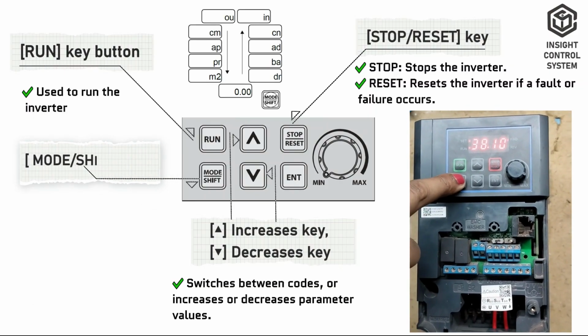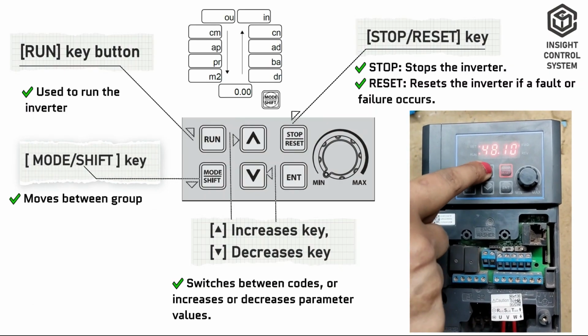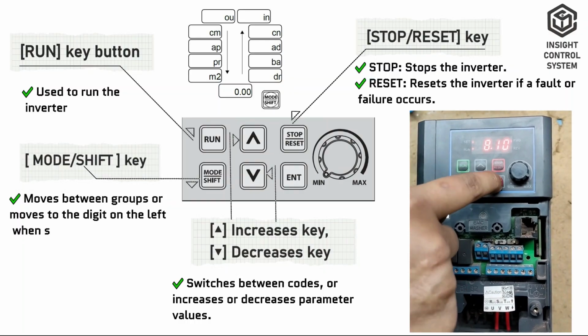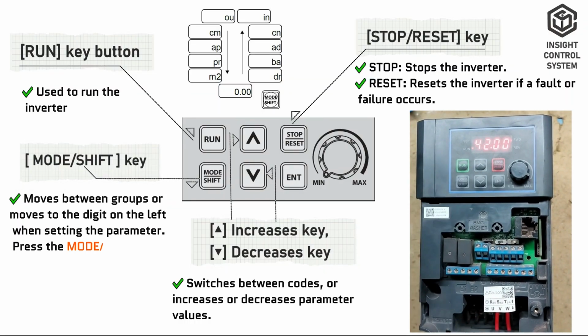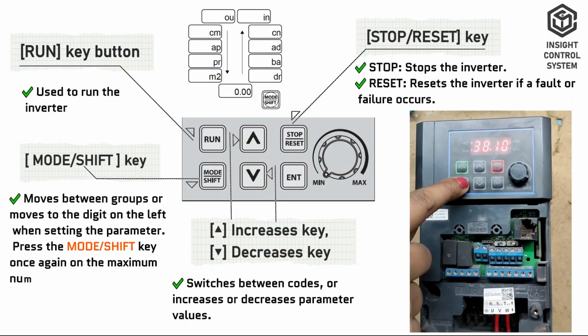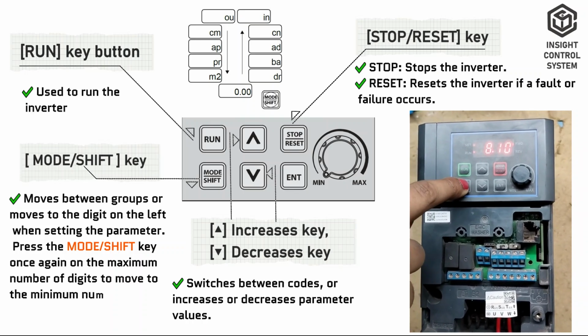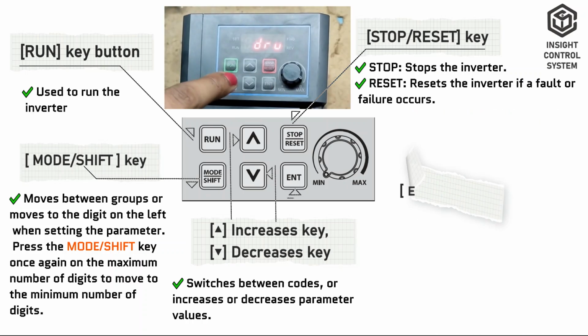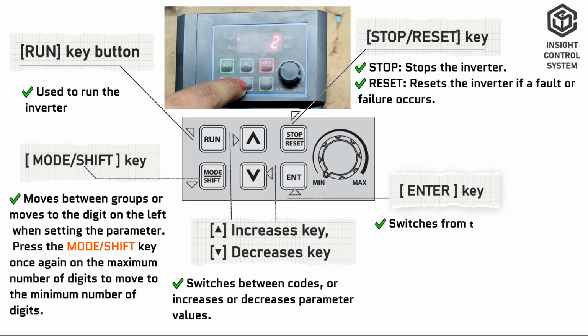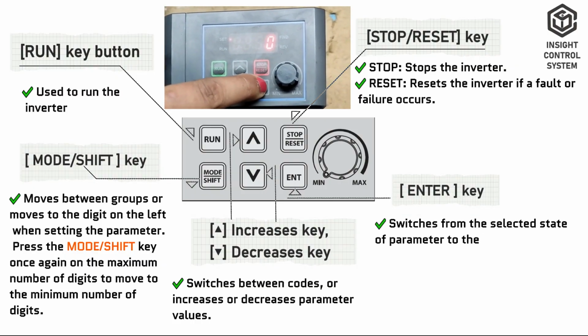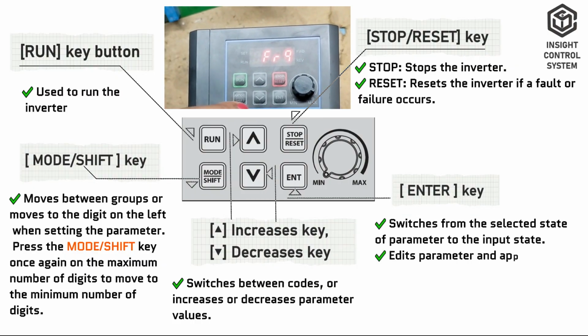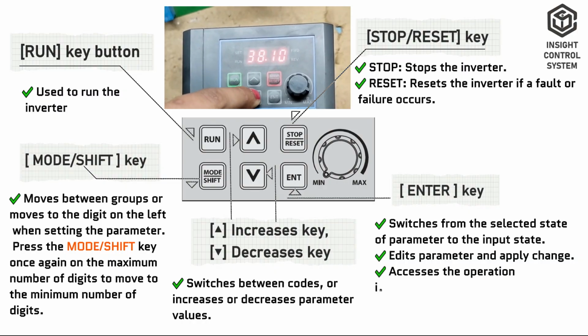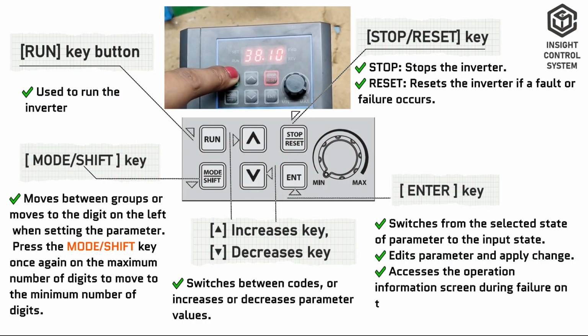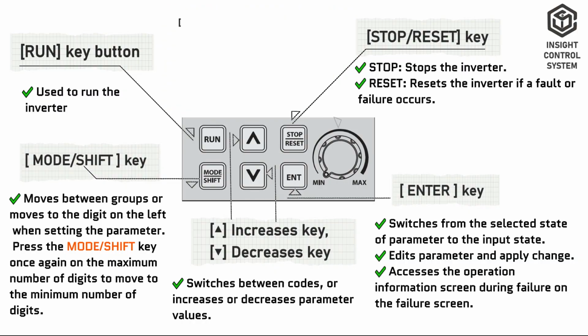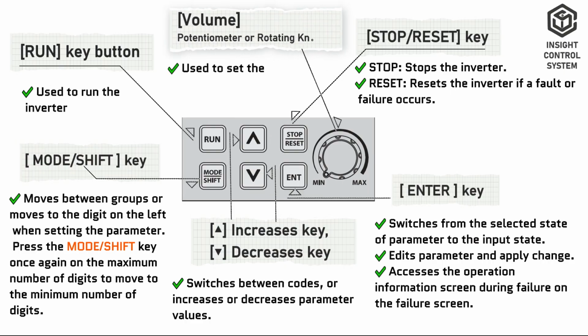This is mode or shift key button, moves between groups or moves to the digit on the left when setting the parameter. Press the mode or shift key once again on the maximum number of digits to move to the minimum number of digits. This is enter key button, switches from the selected state of parameter to the input state, edits parameter and applies change, accesses the operation information screen during failure on the failure screen. This is potentiometer or rotating knob, used to set the operation frequency.